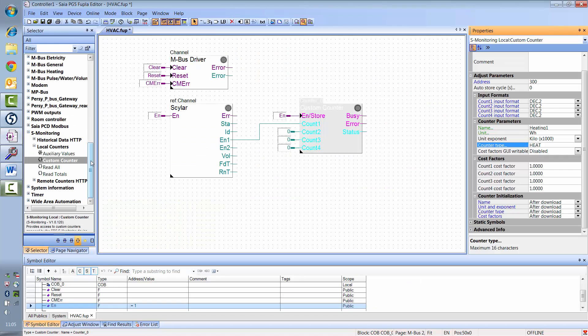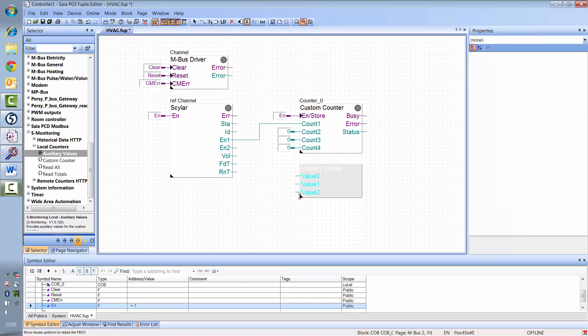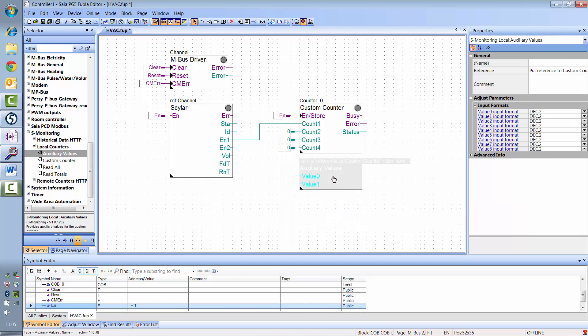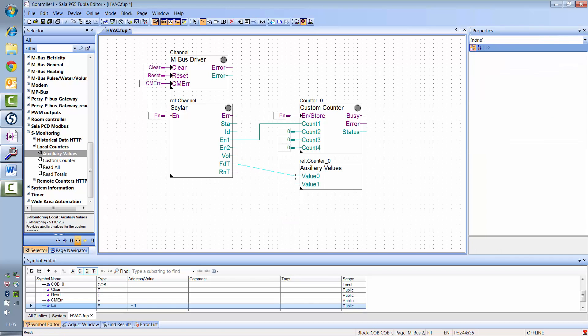Along with the count values from a meter, other values can also be displayed. This is done with the auxiliary values F-box. The auxiliary values F-box must reference the counter F-box. The template for heat meters is pre-configured so that the feed temperature goes to value 0 and the return temperature goes to value 1.